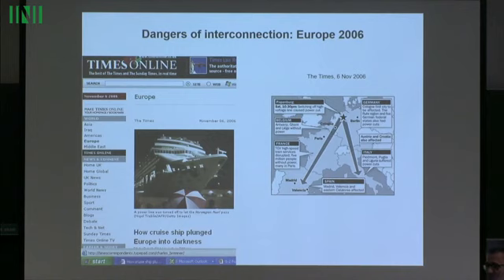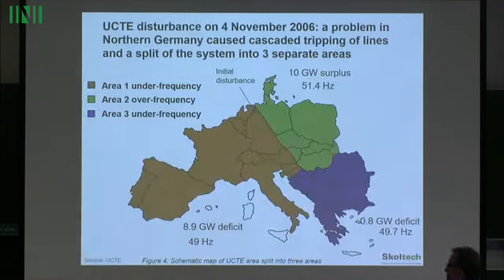Again, the definition of whether it's a blackout or not - system operators don't call it a blackout, they call it system separation. Because what happened wasn't a blackout across Europe; certain customers were disconnected due to local protection, but the whole of continental Europe, which normally operates as one area at one frequency, got separated into 3 parts.